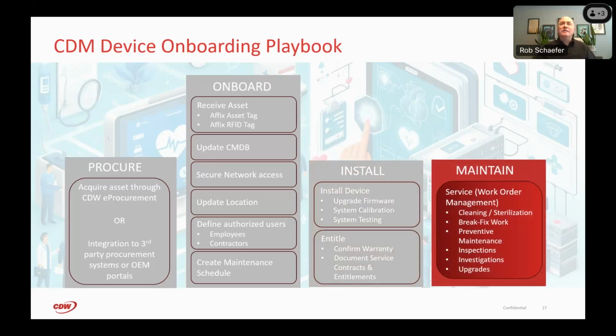And now that the device is active and potentially in use, we need to leverage work orders to document that cleaning and those sterilization procedures by EVS, as well as inspections. We may also address issues via break-fix work or the preventive maintenance and those ever important upgrades. This maintenance is meant to reduce device downtime, keep the equipment at peak performance, and promote a long and useful life of the device. In fact, I would submit when you're doing this properly, you are extending the useful life and availability of that device.